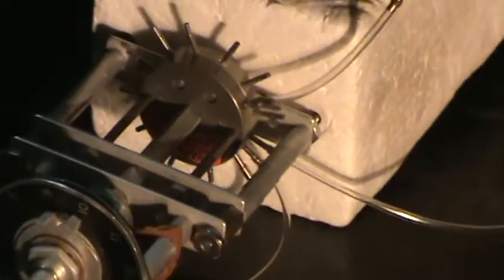If we can identify that, then we know what to pay attention to. So the options that we'll try... this is a stiff spring. We'll try different variations. This is two sets of louvers on a window box, and these are removable, so we can try what the acoustical engineer will probably want to do, which is to cover it all up, to see what happens. We can try taking it off as well to see if that increases flow. We need to find out where the choke point is, and if we need more air, what we can do to increase it.